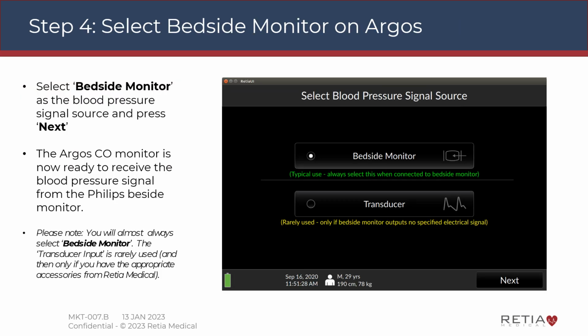Step 4. Select Bedside Monitor on Argos. Select Bedside Monitor as the blood pressure signal source and press Next. The Argos Cardiac Output Monitor is now ready to receive the blood pressure signal from the Philips bedside monitor. Please note, you will almost always select Bedside Monitor. The transducer input is rarely used, and then only if you have the appropriate accessories from Retia Medical.